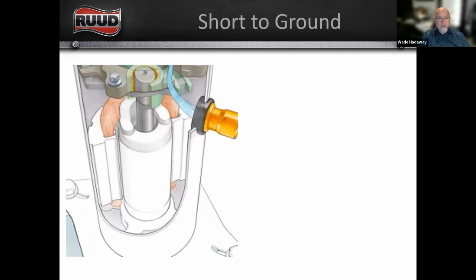And so what does that mean? Here's a cutaway drawing of a compressor, and you can see that pink, sort of copperish material, those are your windings for your compressor motor. And what can happen is, for a variety of reasons, there could be acid in the system, we could be running the compressor hot, or we could be having too much current draw, and that could cause one of the wires, one of the conductors in our compressor winding, to break. And that wire comes loose and it touches the shell of the compressor. So now we have a short to ground, and that's going to trip the breaker.